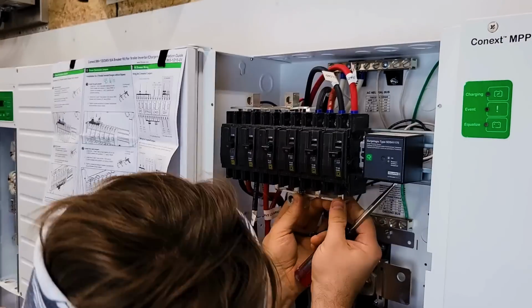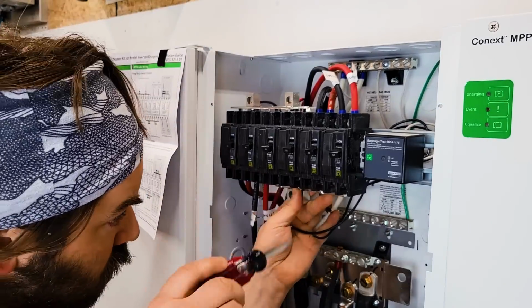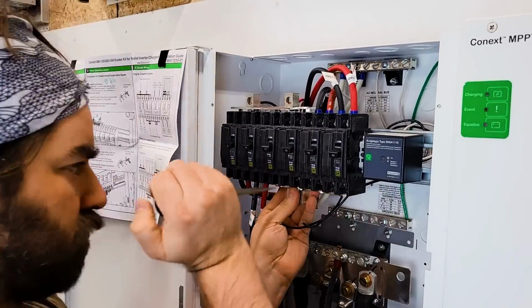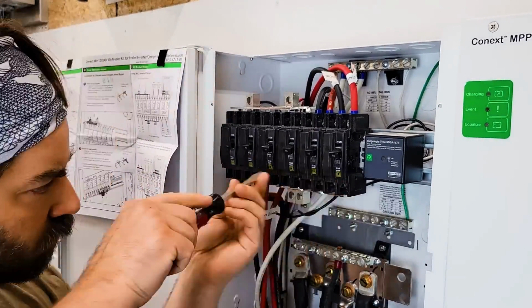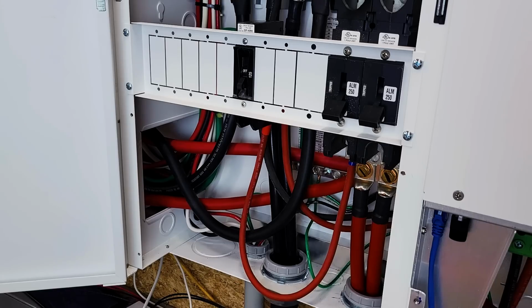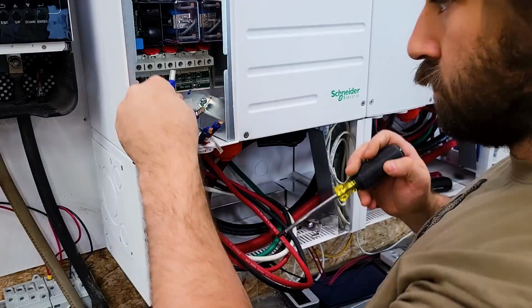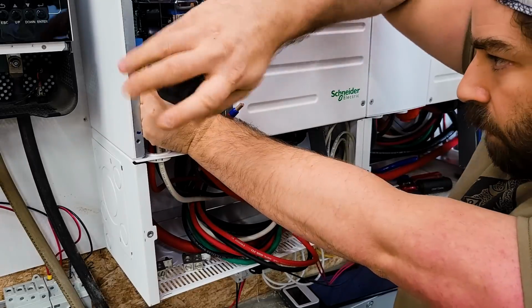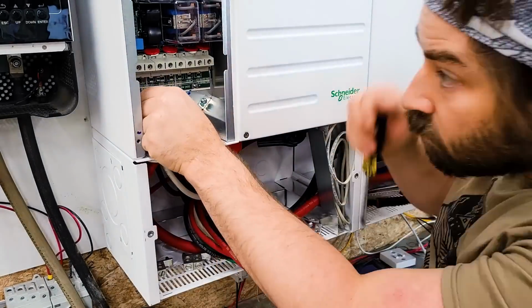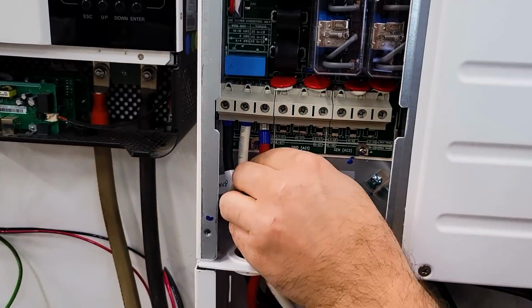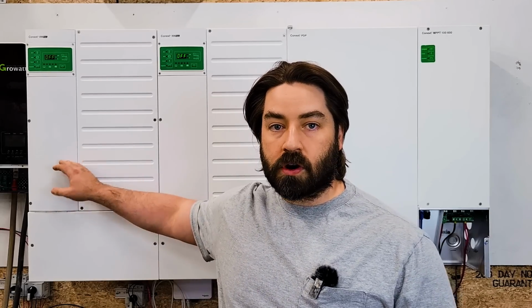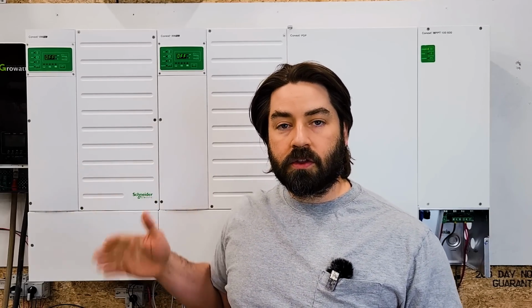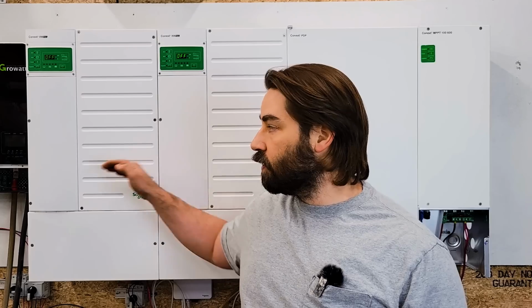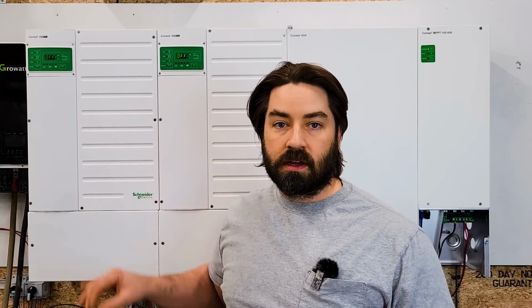The AC load wires, the alternating current wires, are all number 6 gauge. They got crimped on wire ferrules, and they go from the terminal box here over to the PDP. And those are also flexible UL listed wires with that ferrule. It's a nice setup. They're all labeled. Now you're going to have 2 sets of hot wires. One of them is for inverter out to the load panel. The other one is labeled as grid input to the inverter.